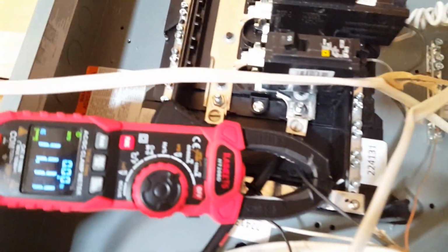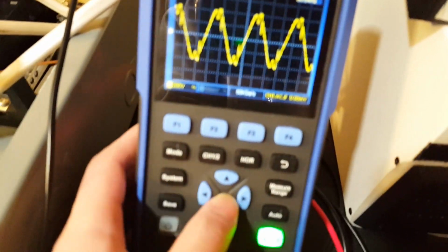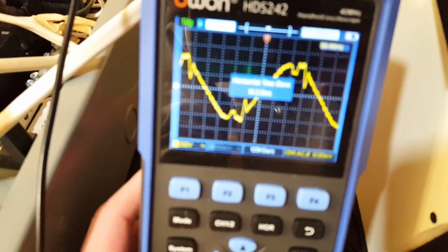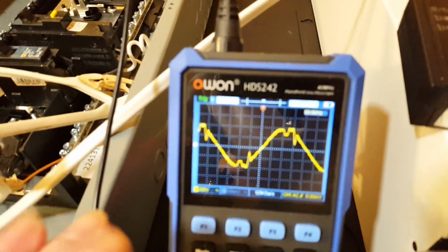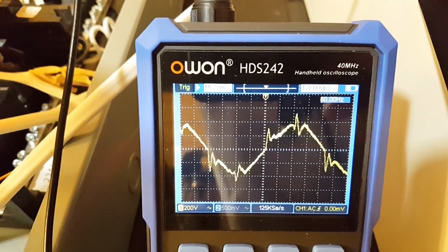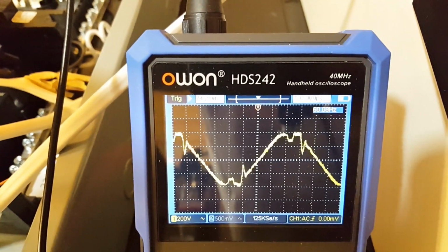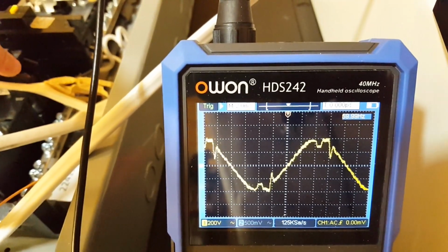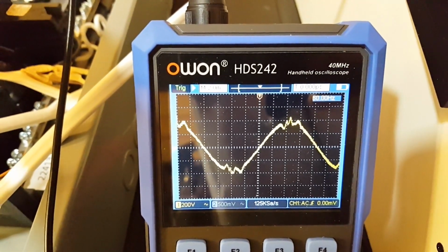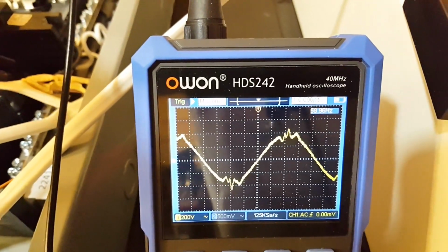Let's check AC running amps. AC running amps at full speed for that vacuum cleaner is 11.11 amps. This is the waveform. That vacuum cleaner can actually distort the waveform a little bit, and it's because it's variable speed. As the motor was getting up to speed, the waveform was changing a little bit. So we're gonna try that again. Look at that. Wow. That is so cool. Okay, that's off.